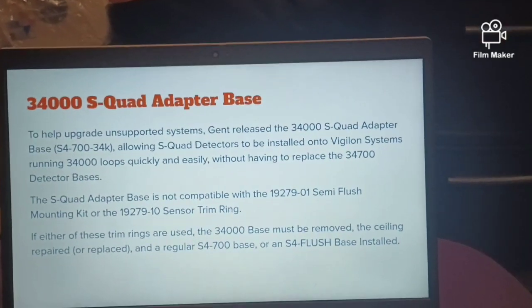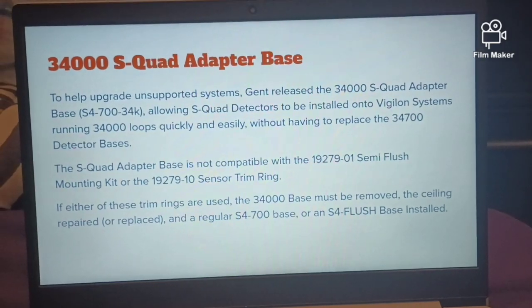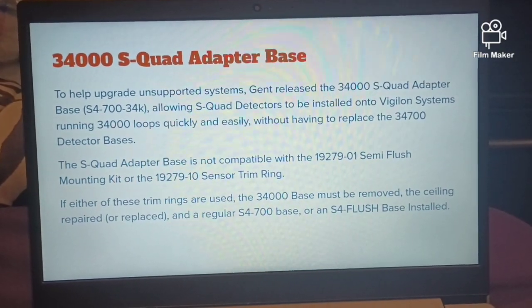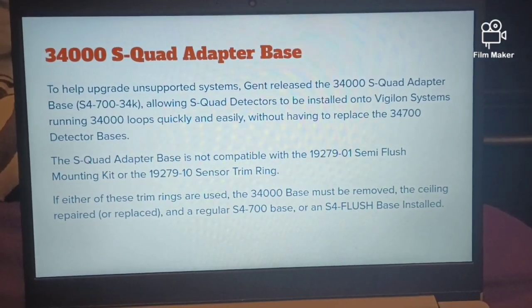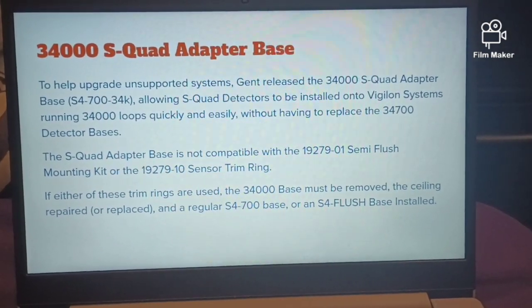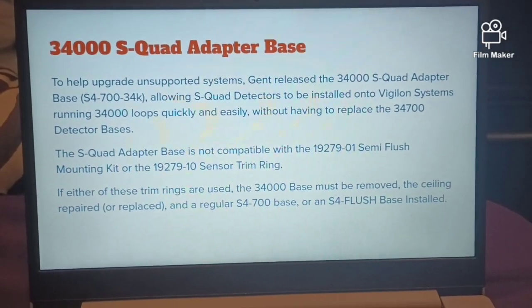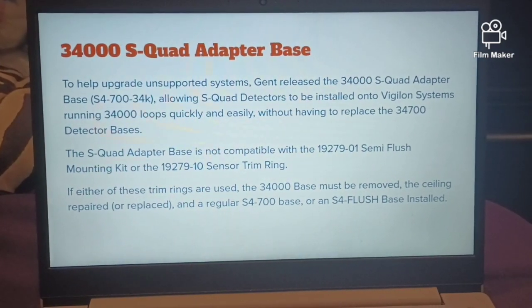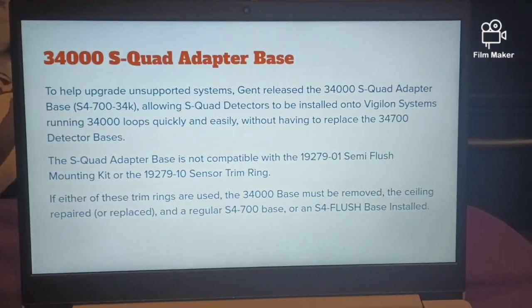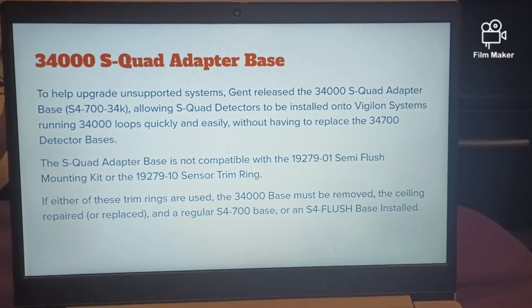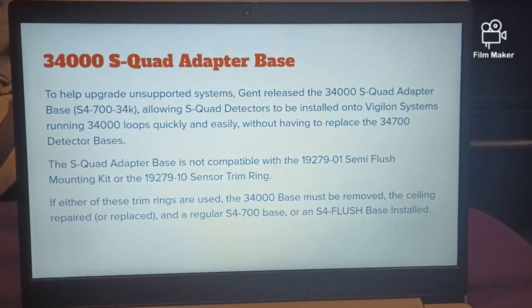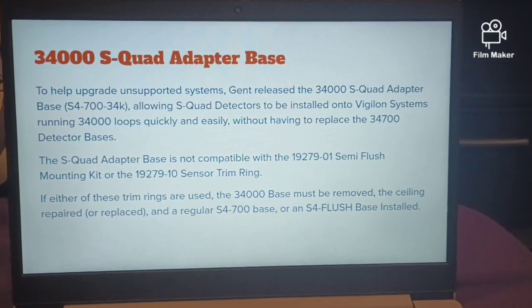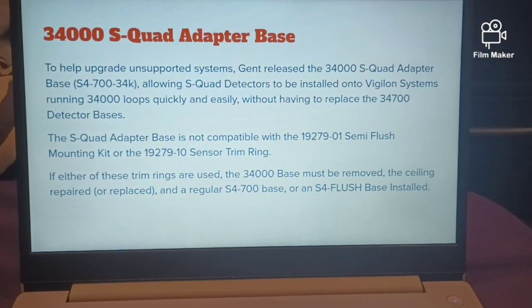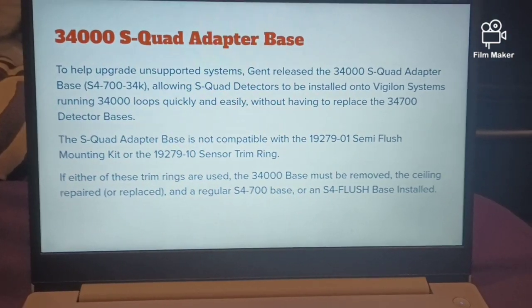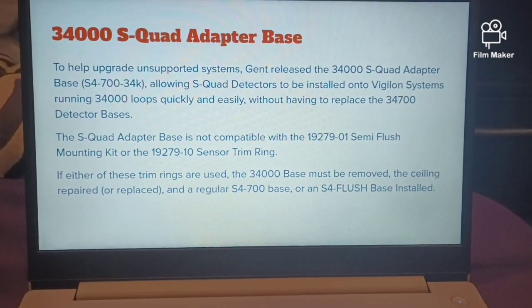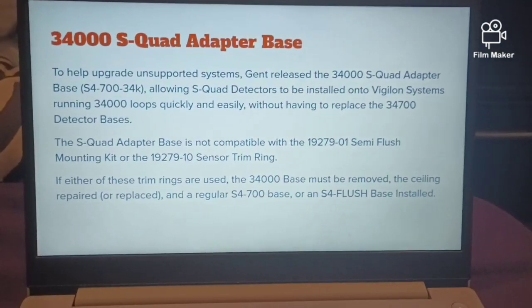34,000 S-Quad adapter base. To help upgrade unsupported systems, Gent released the 34,000 S-Quad adapter base S4-700-34K, allowing S-Quad detectors to be installed into Vigilon systems running 34,000 loops quickly and easily without having to replace the 34,700 detector bases. The S-Quad adapter base is not compatible with 19279-01 system semi-flush mounting kit or the 19279-10 sensor trim kit ring. If either of these trim rings are used, the 34,000 base must be removed, the ceiling repaired or replaced, and a regular S4-700 base or an S4-flush base installed.